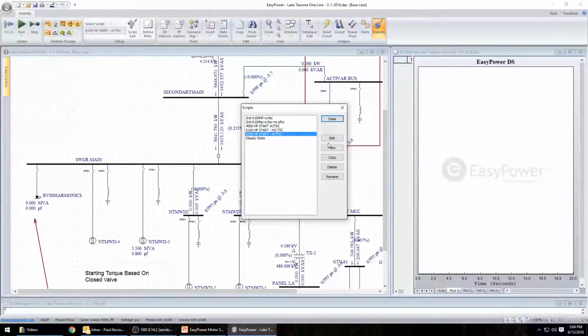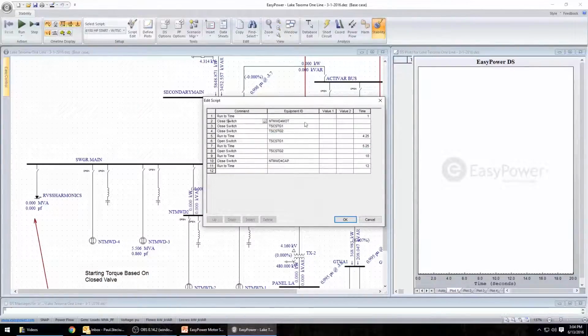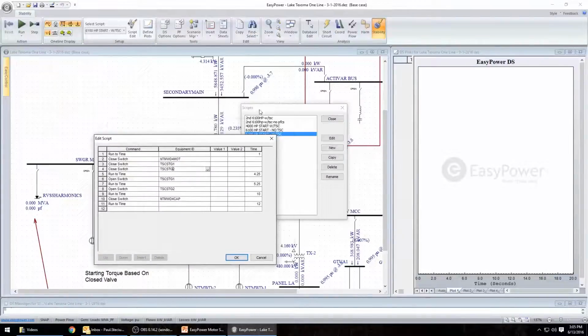6100 horsepower start with TSC, edit, and you can see that we run to time 1 second again, and then we close the number 4 switch, which is what feeds this motor. We also close TSC stage 1 and TSC stage 2 switches here, and that represents these 2 switches here, which feed the actiVAR. So we're switching on the 2 actiVAR stages to simulate the energization of the capacitors. And then we run to time 4.25 seconds, and turn off stage 1. Then we continue the simulation, run to time 5.25 seconds, and open stage 2, and then run to time 10 seconds.